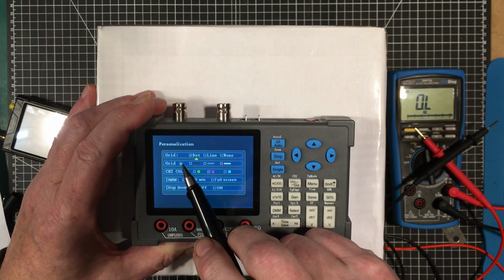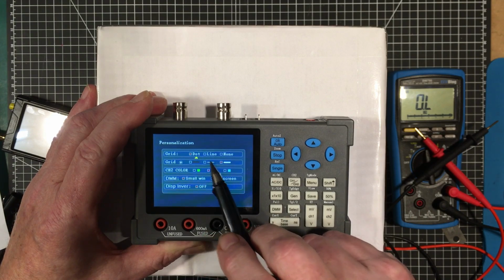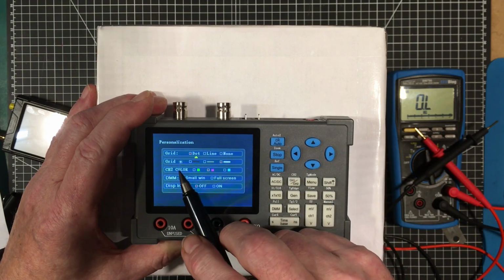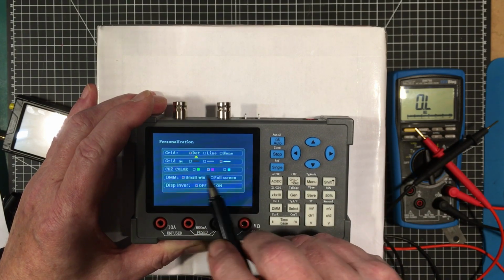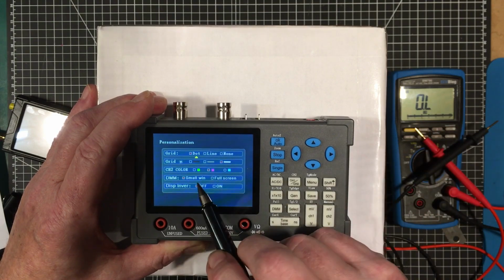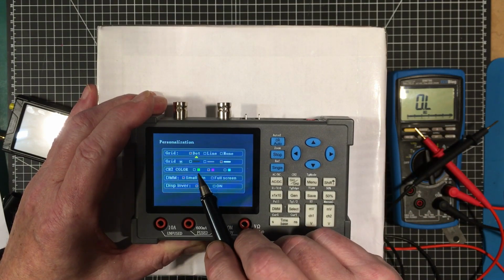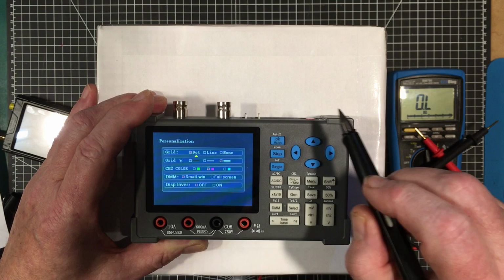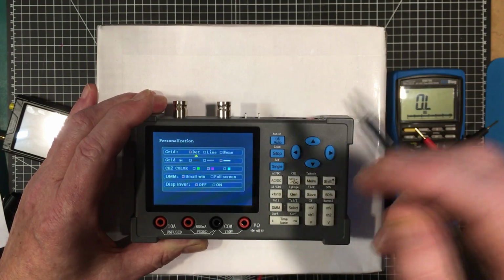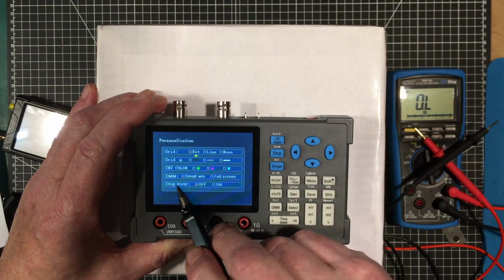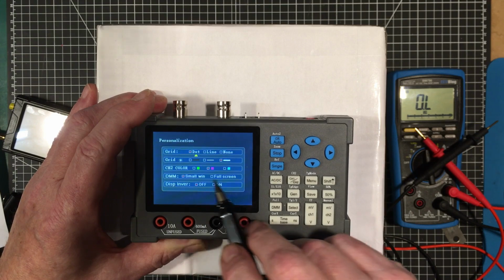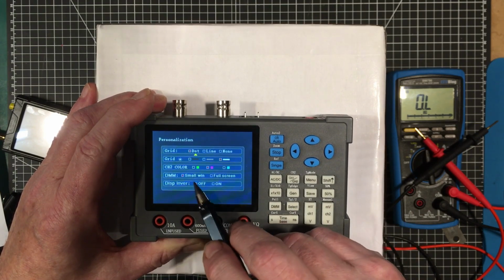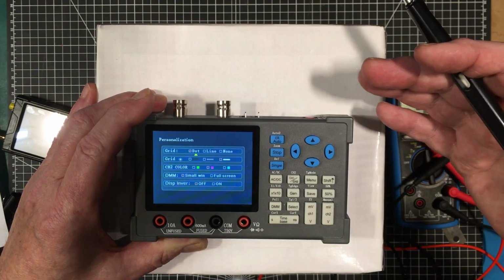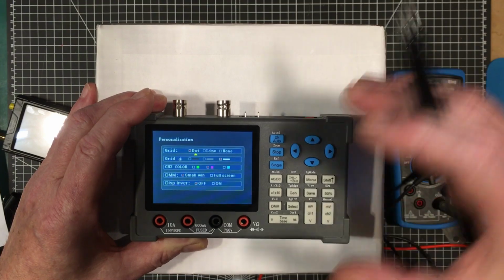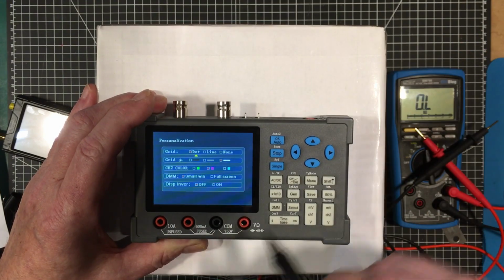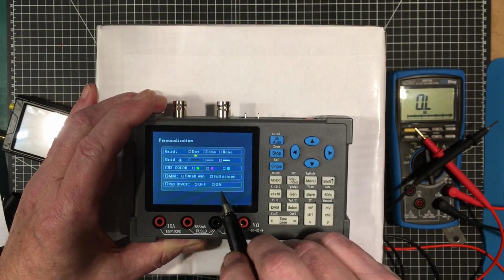So you can choose what kind of graticule you have, whether it's dot, line, or none. You can choose the grid brightness, color of the different channels. Channel 1 is always yellow, but you can choose channel 2 as being green, pink, or blue. I'm going to go with the pink because that's the way it came. You can change the default window for the digital multimeters, small window or full screen. I would go with the small one because you can use the multimeter while you're using the scope and it's handy not to have it wipe out everything you're looking at on the scope. And you can choose whether to invert the display or not.